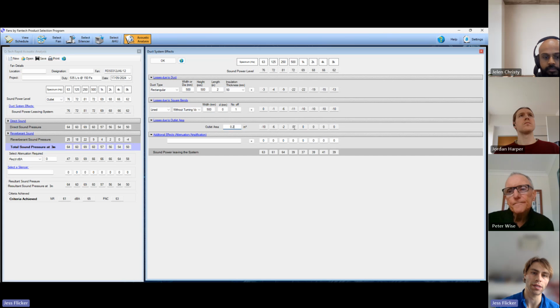So if you're trying to do this modeling with multiple outlets, do you include the duct losses and square bends for all of the outlets, or is there an index run, so to speak, for the acoustics? It basically is an index run, yeah. And generally, it's going to be the closest to the fan. So you'd only do this modeling for that one, because the sound will continue to attenuate the further you go down a duct system. Okay, so if you attenuate the first outlet sufficiently, then the rest of the system will be fine. Does that make sense? You're always looking at the closest outlet to the fan, to attenuate the fan noise.